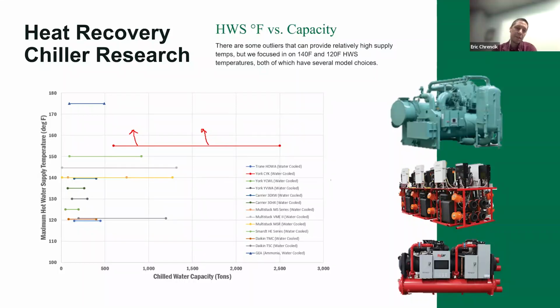They also have a screw machine, a 200-tonner nominal with duplex screw compressors, and that can get you effectively a 4-to-1 turndown: shut a compressor off and ramp one of them down to 50%. That can get you 176 degrees, I think, peaking out. Then you've got other players like Oilon, which has a duplex screw machine, same thing, but they get 160. They have a piston machine with little 10-ton modules that can get you 180 degrees. And all of these temperatures are simultaneous with 42-degree chilled water coming out too. So we're talking 42-degree chilled water with 170 to 180 degree hot water.